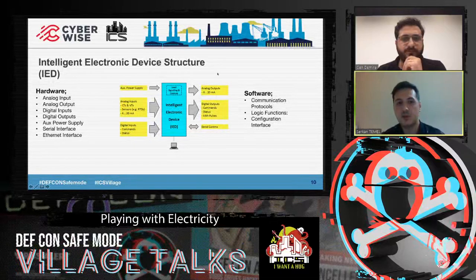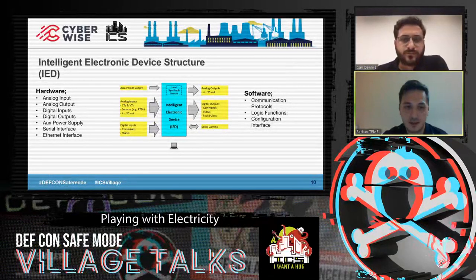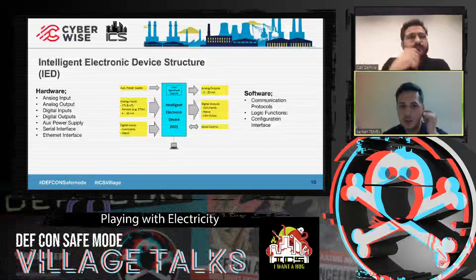Digital inputs and digital outputs are mostly critical, because digital inputs basically come from the circuit breaker position, isolator position, and other information about the physical systems. Digital outputs control the circuit breakers, meaning that you control the electricity. Because of that, in SCADA systems, most communication protocols, anomaly detection, and from a cybersecurity perspective, we focus on the digital output signal. In the beginning these devices had a serial interface, because at that time there was no Ethernet IP world. Today most devices have an Ethernet interface and gain the advantages of the Ethernet IP world. But these advantages also cause side effects from a cybersecurity perspective. I will talk about that later.